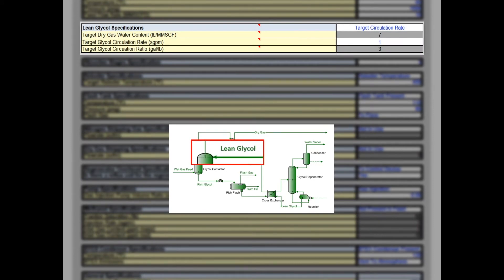The purpose of a glycol dehydration unit is to remove water from the feed gas to prevent hydrate formation and to meet contractual pipeline specifications downstream. While TEG does a good job of removing water from the system, it also absorbs some hydrocarbons in the process. The higher the TEG rate circulated in the dehydration unit, the higher the absorption of hydrocarbons, and in turn, the higher the emissions will be.